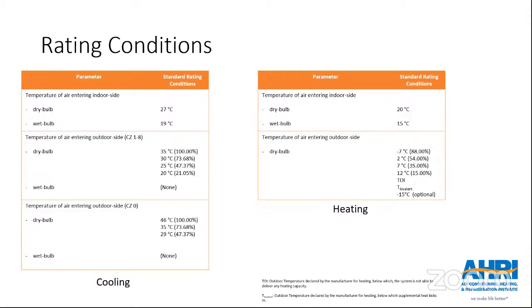One major concern I always have, and somebody also pointed out in the question, is the effect of humidity. Many Indian cities have ambient temperature close to 25 degrees, but very high relative humidity. Going by the load line in this standard, 25 degrees centigrade corresponds to 47% load, whereas in a city like Mumbai you may have 100% load at 25 degrees ambient temperature. That makes the testing irrelevant. So how is the global standard addressing such situations, and trying to bring the test values close to the field performance of the systems?